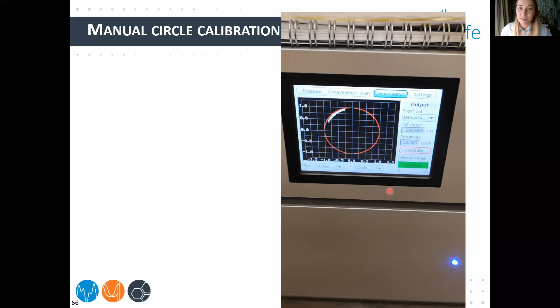Another thing you can have is that the signal becomes like a line on one side. That means it drifted that much, or most likely you calibrated it while it was drifting, and then when it stabilized, the signal is completely in a different area. If it's that much off, first you can still try to do manual calibration. And then afterwards, if it's still off, just redo the wavelength scan, then do this manual calibration, and then you can continue with your experiments. So it's not a big issue. You can very quickly fix it just being in the sample dish. You don't really need to go back to the original dish.